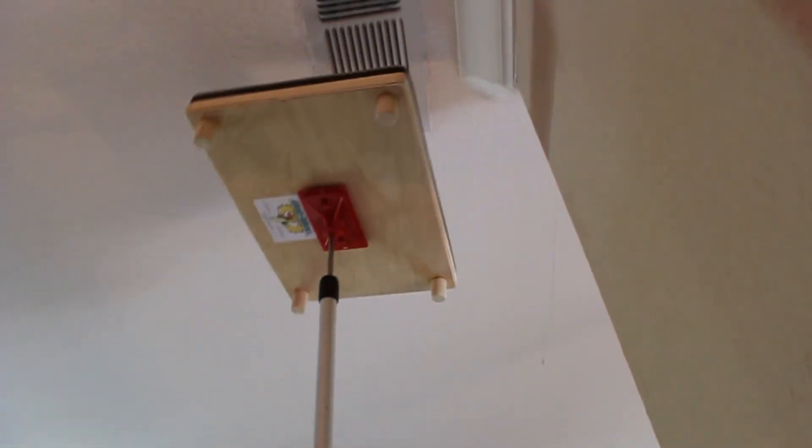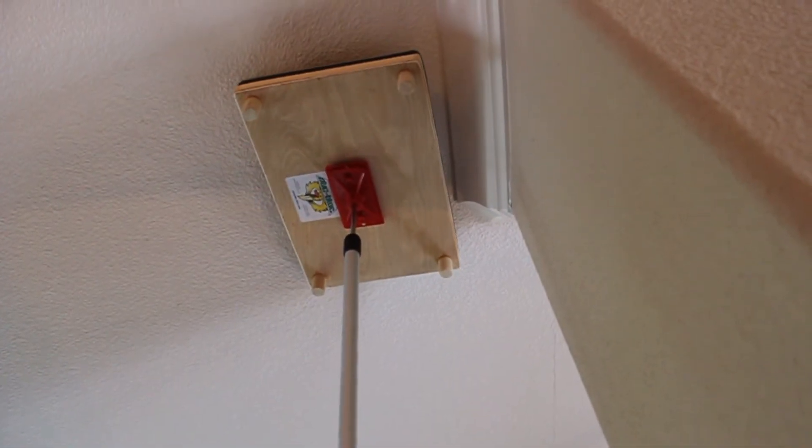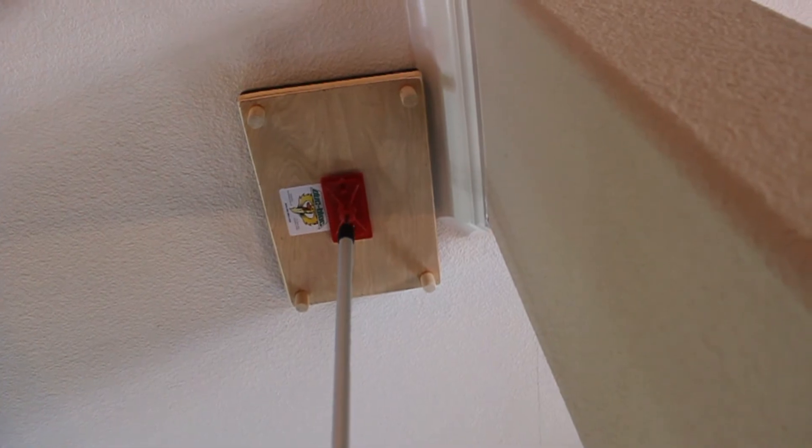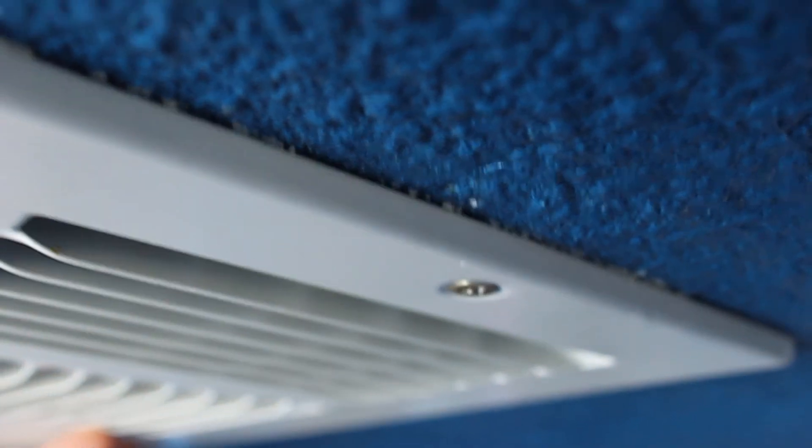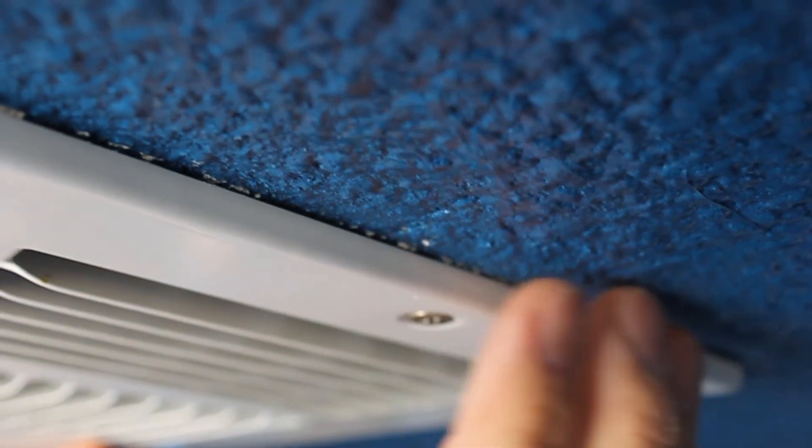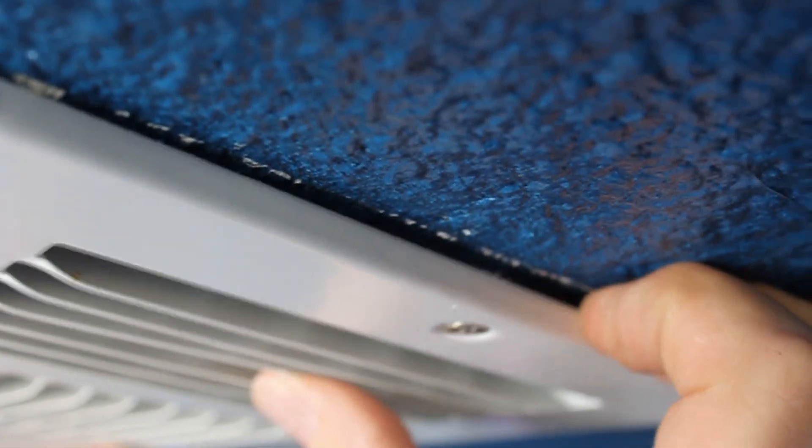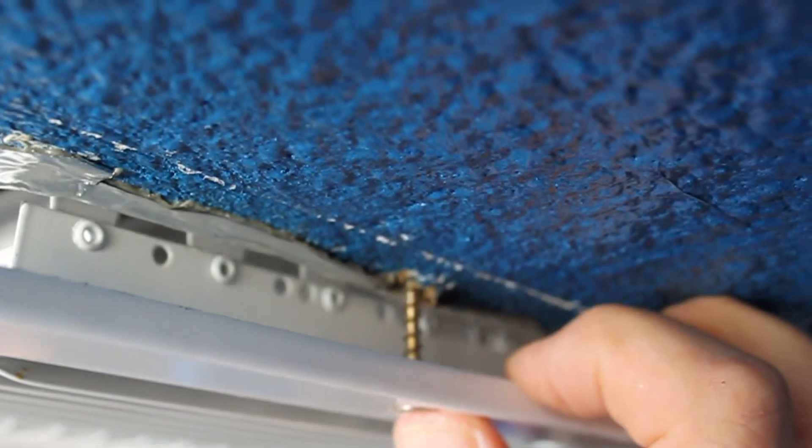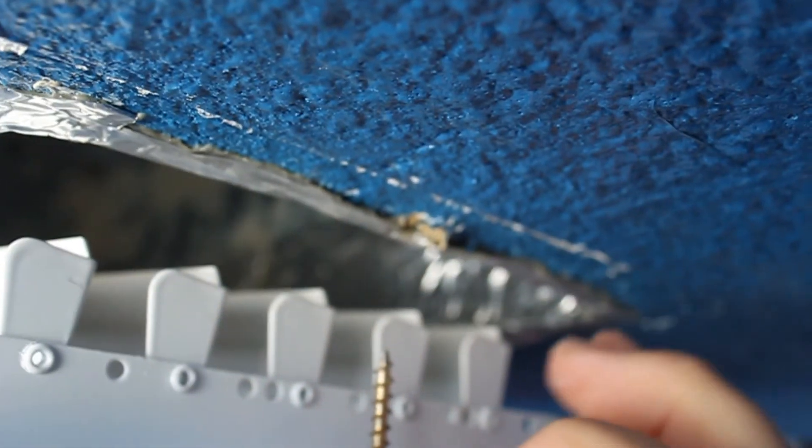The main advantage of duck blocks over other register sealing devices on the market is that duck blocks are braced against the floor and push up against the ceiling rather than pulling on the register. Some registers are only held on by a couple screws going into sheetrock. That's not much to support the weight and pull of the device plus the 50 pascals of pressure being exerted on it.